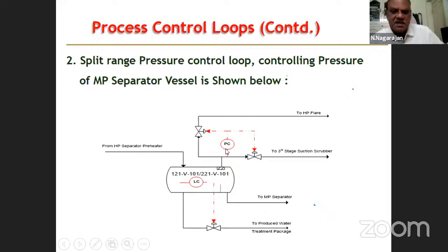The pressure control is here. This is the main gas outlet. And this is the excess pressure to the HP flare. This is a split range. So this measures as long as the pressure is within the operating pressure of this equipment, the flow will go through this. This will only control this valve. When the pressure exceeds the set point, what will happen? It will start allowing this valve to open and release the excess pressure to the flare. So the normal pressure stream will go here. The excess pressure will be released to this. A split range controller, and this is a normal level controller.